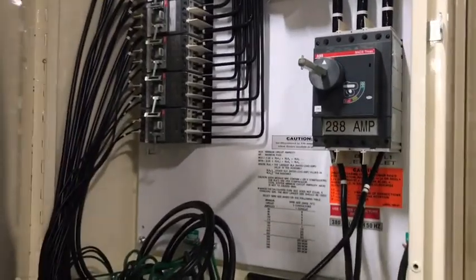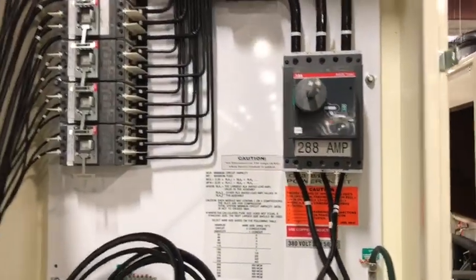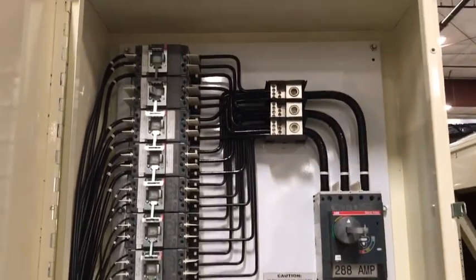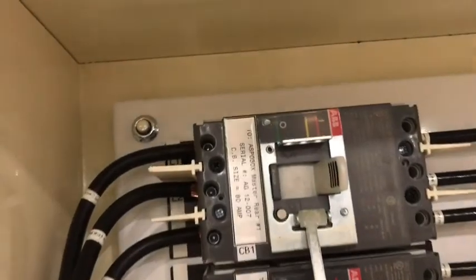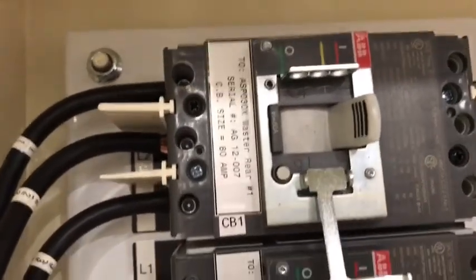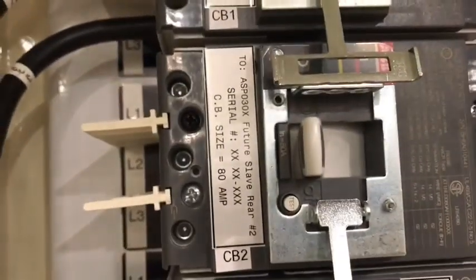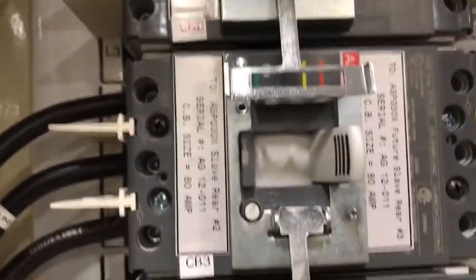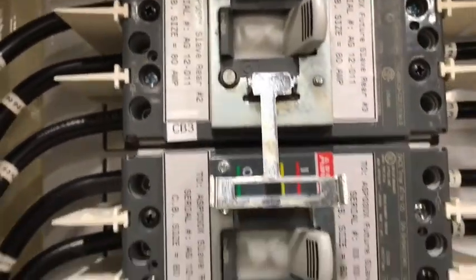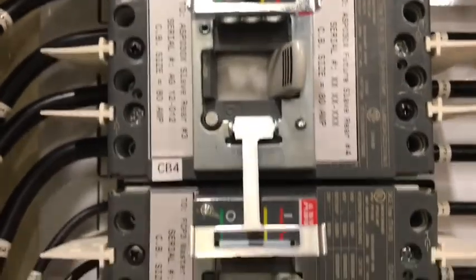And we'll take a tour of this module. We have a door interlock disconnect circuit breaker there with power coming up through that, through a power distribution block, and then to individual mechanical circuit breakers. And these feed mechanical modules and free cooling modules, and you can see the labels on them to determine which module is being fed from which breaker.